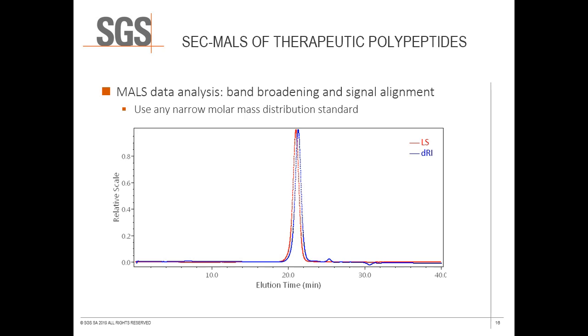Even with minimizing the tubing volume between the two detectors, the sample band inevitably broadens as it travels from one to the next. By selecting this peak as the reference for alignment and band broadening, the software snaps the peaks into a near-perfect overlay. It is important that the standard used for this correction be narrow in molar mass distribution, so that the peak shape and apex retention times should truly align. We used a narrow 17 kilodalton polymethylmethacrylate standard for this correction.